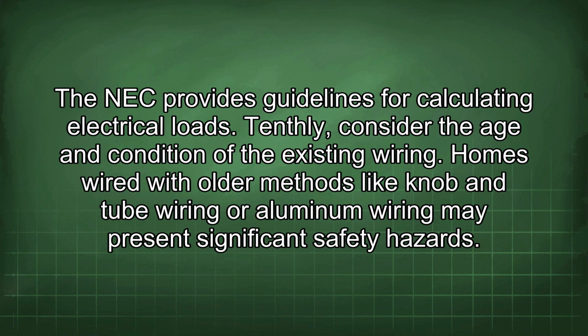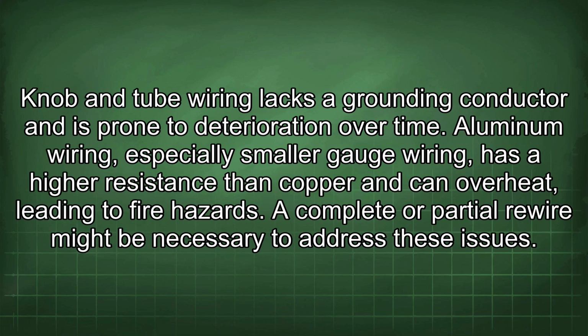Tenthly, consider the age and condition of the existing wiring. Homes wired with older methods like knob and tube wiring or aluminum wiring may present significant safety hazards. Knob and tube wiring lacks a grounding conductor and is prone to deterioration over time. Aluminum wiring, especially smaller gauge wiring, has a higher resistance than copper and can overheat, leading to fire hazards. A complete or partial rewire might be necessary to address these issues.